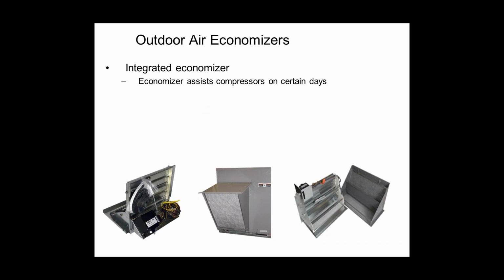Integrated economizer means I'll run the fresh air cooling along with the compressor cooling as needed. Economizer is my first stage. If it's good outside, compression is my second stage. Right? So I need to do that. It's required by code to do an integrated economizer.